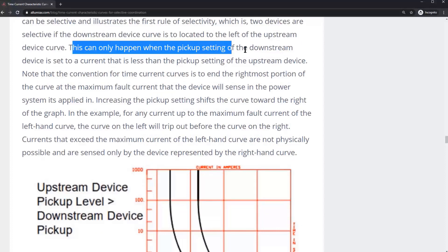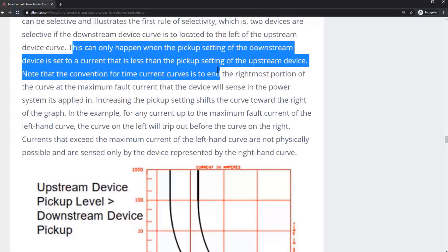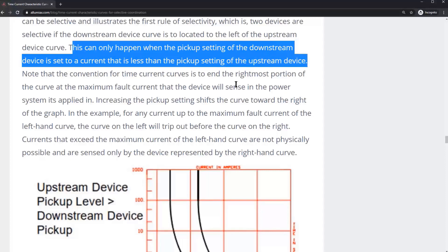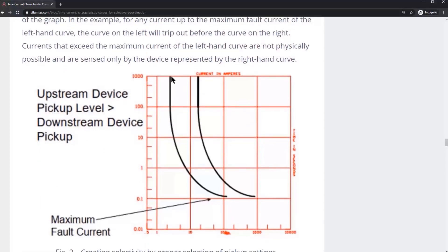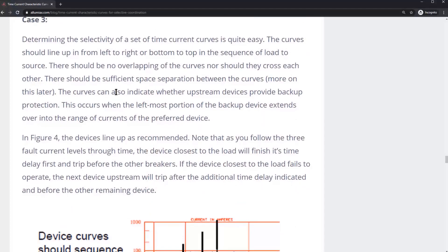This can only happen when the pickup setting of the downstream device is set to a current that is less than the pickup setting of the upstream device. This pickup value is for the downstream device, and this pickup value is for the upstream device.